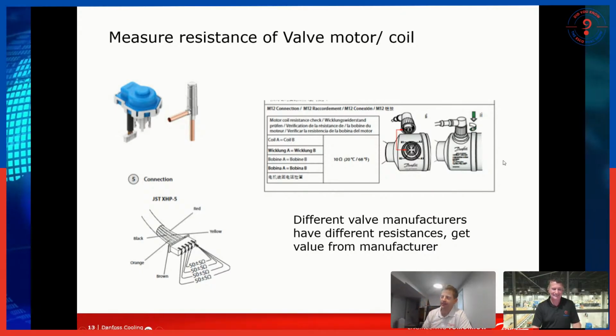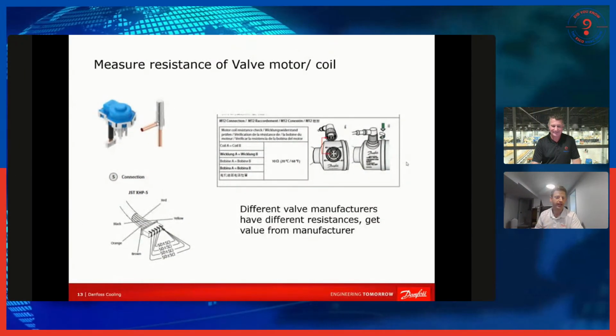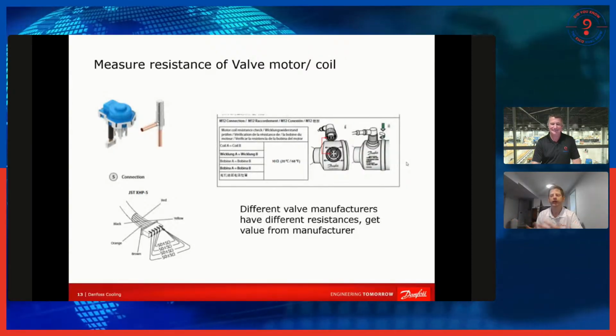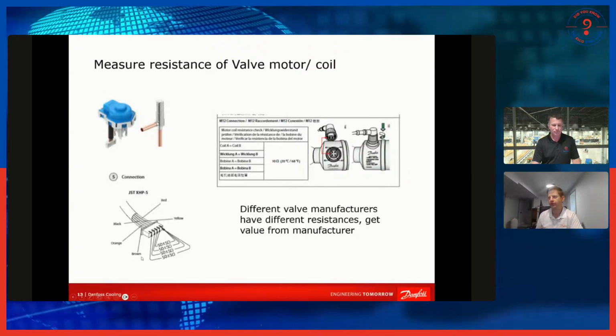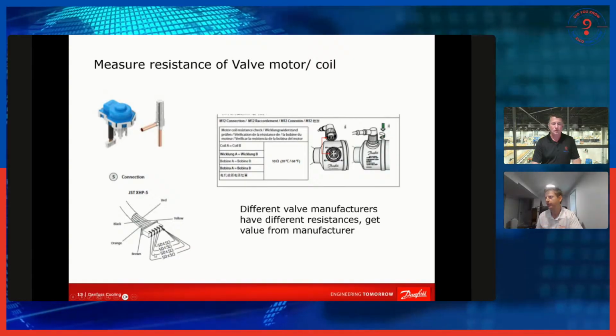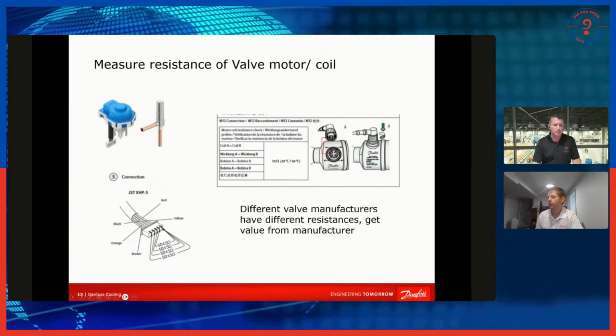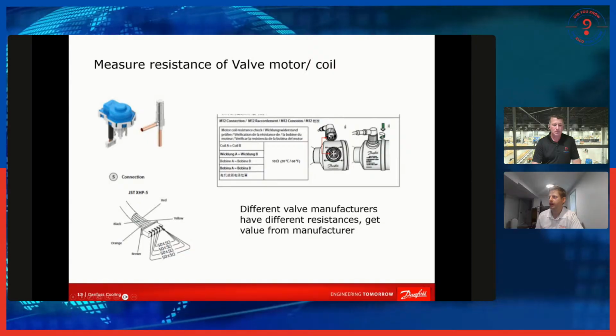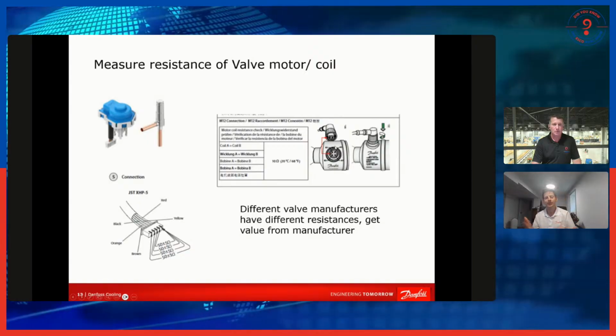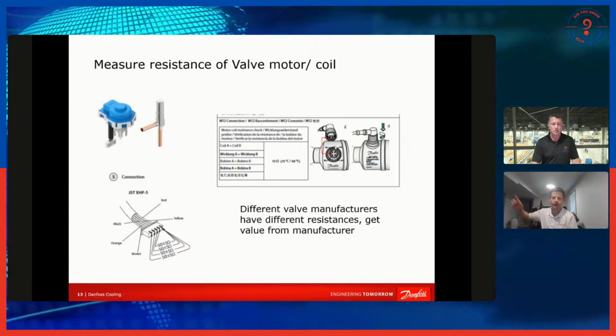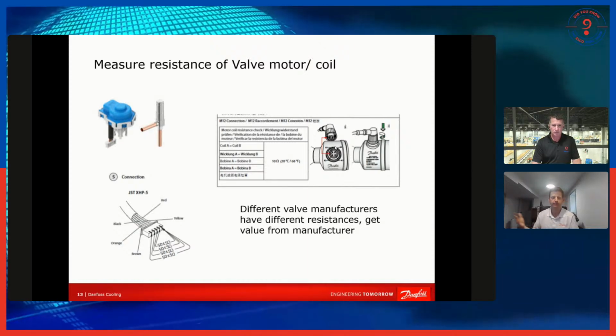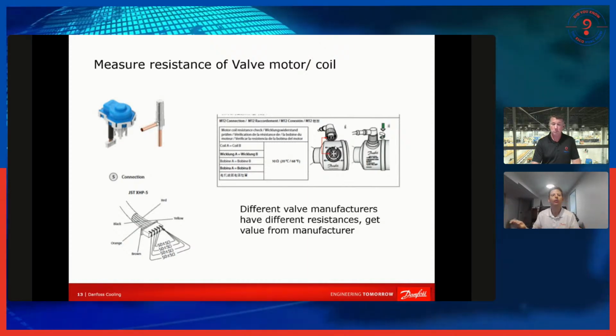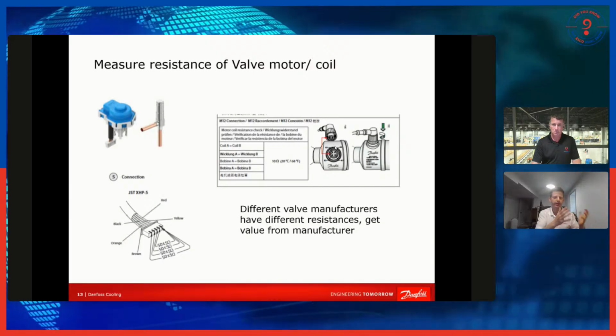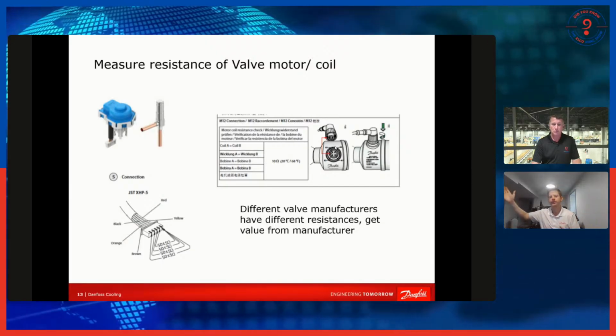So that's a way you can just troubleshoot, give yourself a quick, easy check. Hey, does my motor work? Just pull the wire off the controller and measure it that way. Also, when the cable is separable from the EXV, you can simply check, do I have continuity back to my controller? Did a wire get cut somewhere between where the evaporator is and the controller?